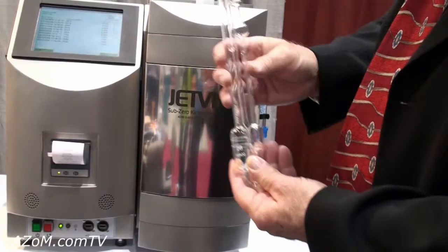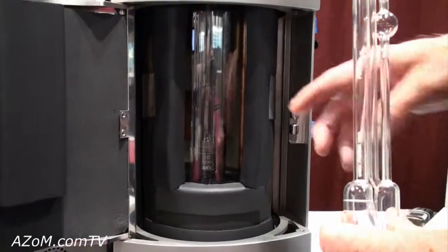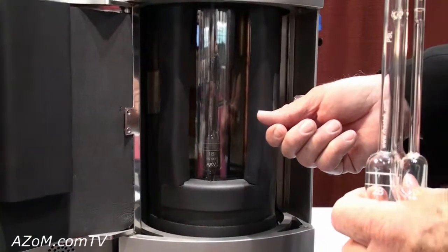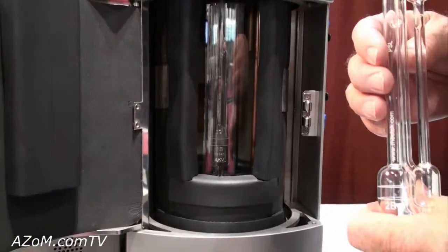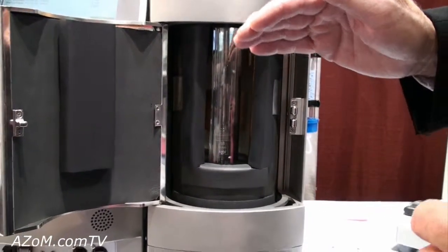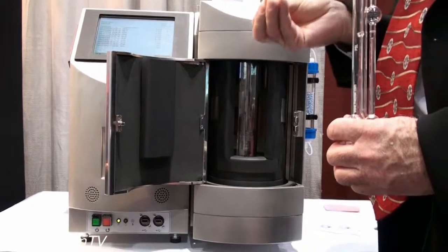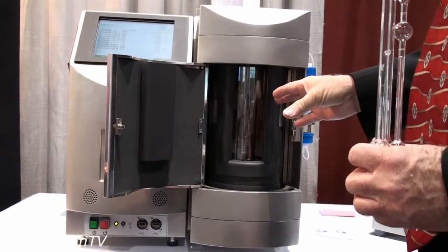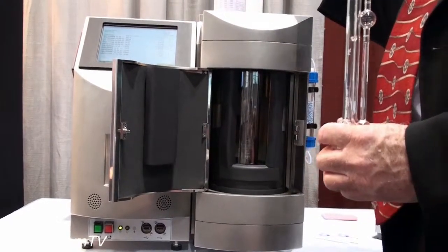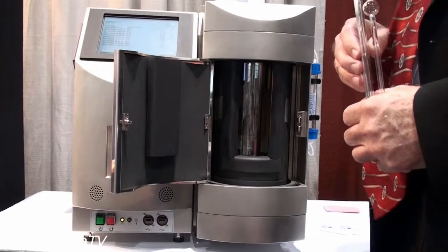The sample and the viscometer would be mounted in a temperature control bath. This bath is unique because it's capable of reaching sub-ambient temperatures down to minus 20 or minus 40 degrees C. There's a requirement for jet fuels to automate the viscosity testing, and this same bath can be automatically ramped up to plus 40 degrees C to run applications like diesel fuels, which also have viscosity specifications.